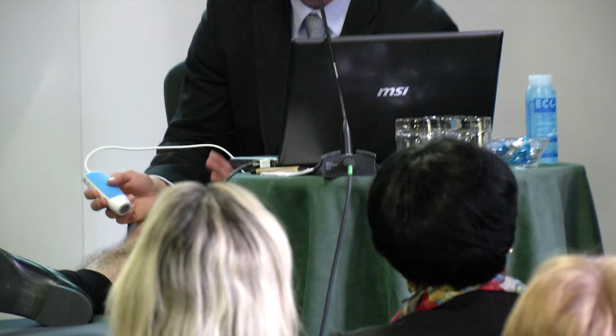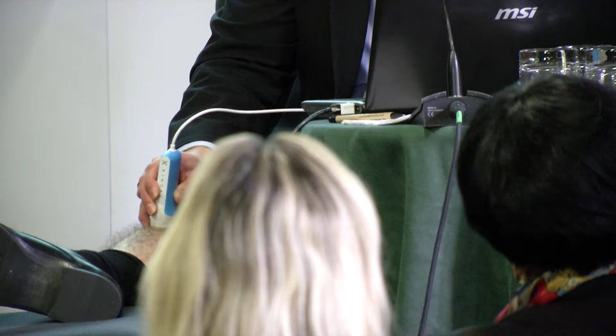Now we have a connection to the computer, so now we are on the same phase. I calibrate the device, and now measuring is on. Now I will move the transducer over the bone, and when I clearly see those 2 echoes, I stop the movement, and the software accepts the signal. This way, I repeat the measurement 5 times. And that's it. We can now see those 5 measurements.